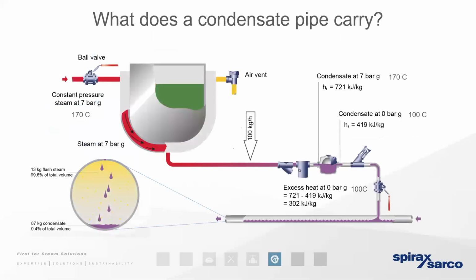So one of the things that really causes a lot of problems on our client's site is they overlook the value of condensate. They underestimate the true value of that condensate. And that's because they may not be handling it correctly, or they may not be giving it the due respect it deserves. So this little graphic that we've gone through previously hopefully will emphasize the benefit that condensate has.